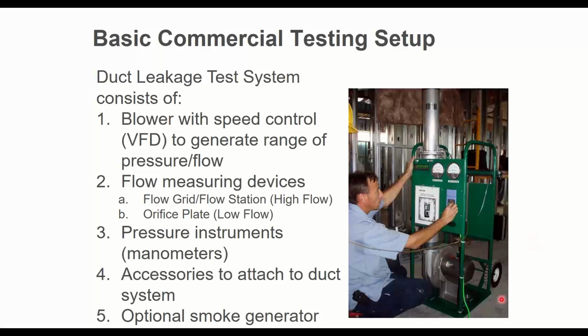If you're savvy about it, especially if you're trying to solve the problem as opposed to pass a test, you'll use a smoke generator, one of those theatrical ones that is basically an electrical box. And it emits smoke into the air, you know, for theaters and stuff like that. You can put that right here on the ground next to the inlet of the fan, and it'll suck that theatrical smoke in. And then you'll be able to see where it's leaking out in the building, and hence you know where you got to go make your duct repairs.